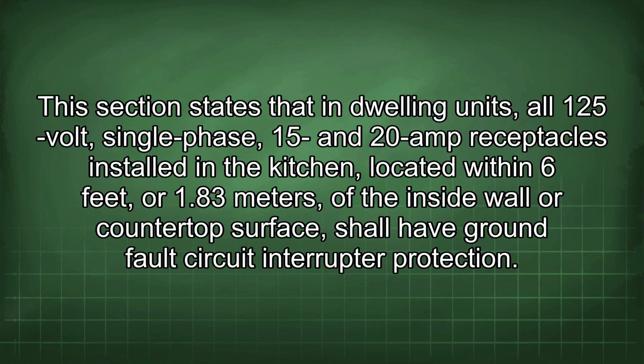This section states that in dwelling units, all 125-volt single-phase 15 and 20 amp receptacles installed in the kitchen located within 6 feet or 1.83 meters of the inside wall or countertop surface shall have ground fault circuit interrupter protection.